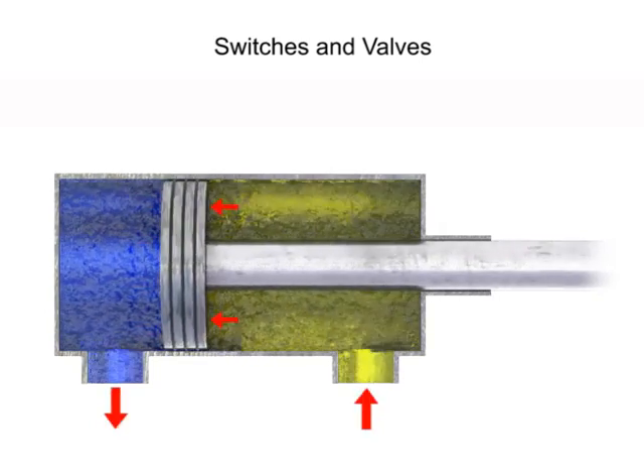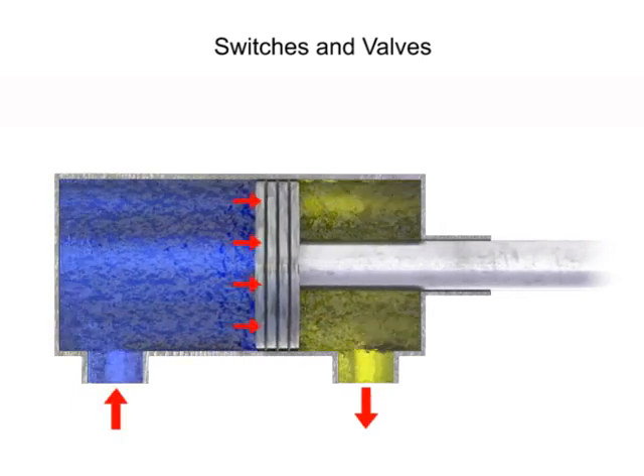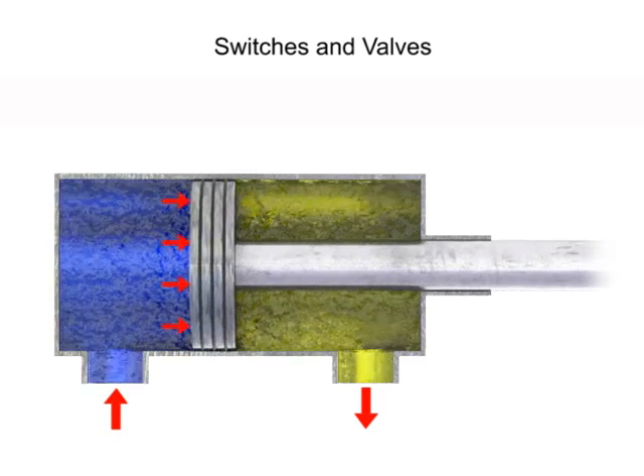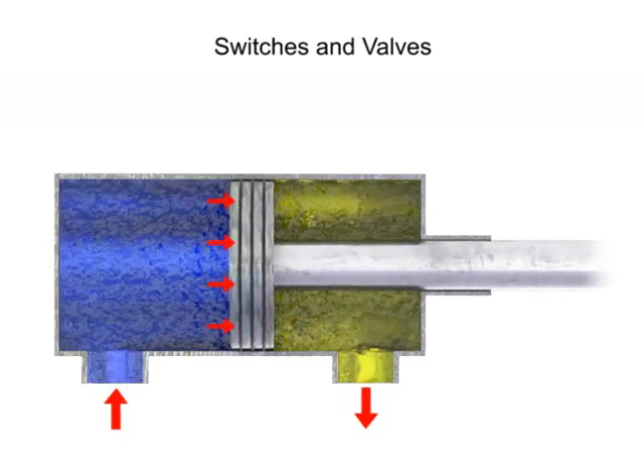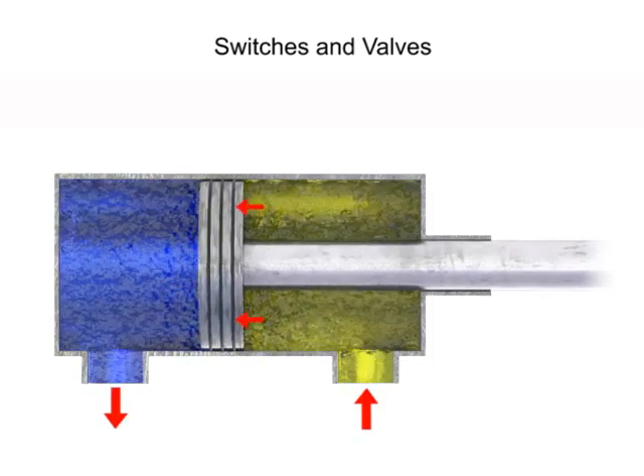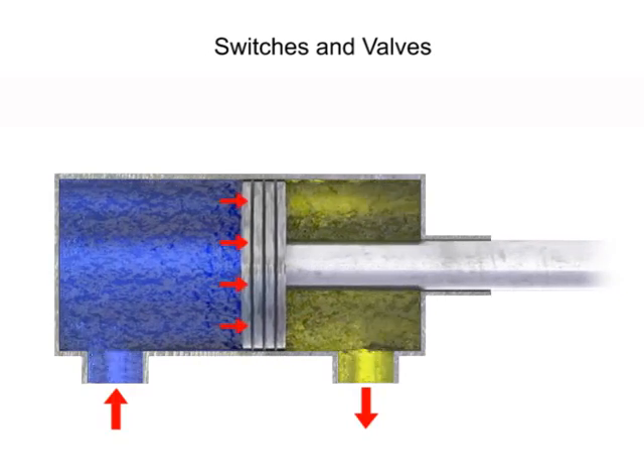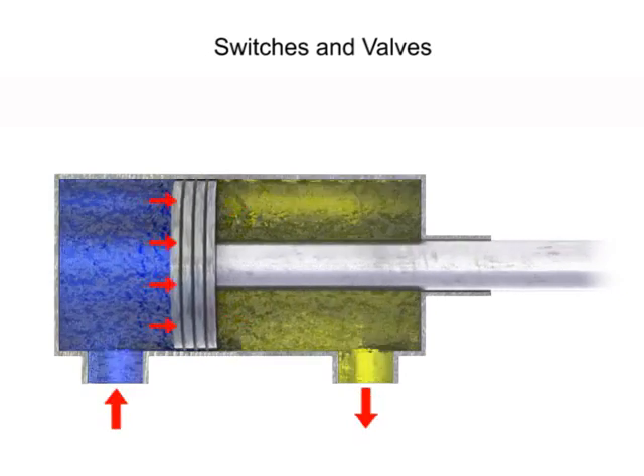In an air cylinder, automatic reciprocation can be stopped by an electrical action or by a shut-off valve in the airline. If stopped by electrical action, it will continue to travel until it reaches one end or the other of its stroke. If stopped by shutting off the air, it can be made to stop anywhere in its stroke.